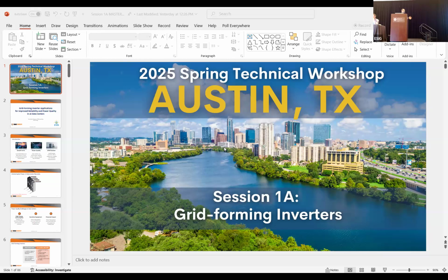And we are assessing all the projects. We have model quality testing benchmark. So we run automated tests to do the model quality testing. We do it ourselves in-house at the IESO. We run more than, I would say, 700 tests for each IBR, testing at different operating points, different configurations.